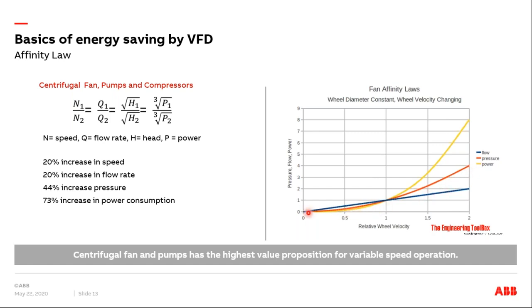And the power consumed by the fan, pump, or compressor connected to a motor has a cubic relation with the speed. So if the speed of your motor connected to a fan or a pump is increased by 20%, your flow rate would increase by 20%, but your power consumption actually increases by 73%. So you want to be operating at lower speeds if the situation allows. And we know that in most cases, you never operate things at 100% load anyway. So if there is a possibility of reducing the speed, we should do that. And VFD allows you to make this change and go to a different speed. Whereas in a traditional system, it's directly connected to the line and you operate at one speed only.